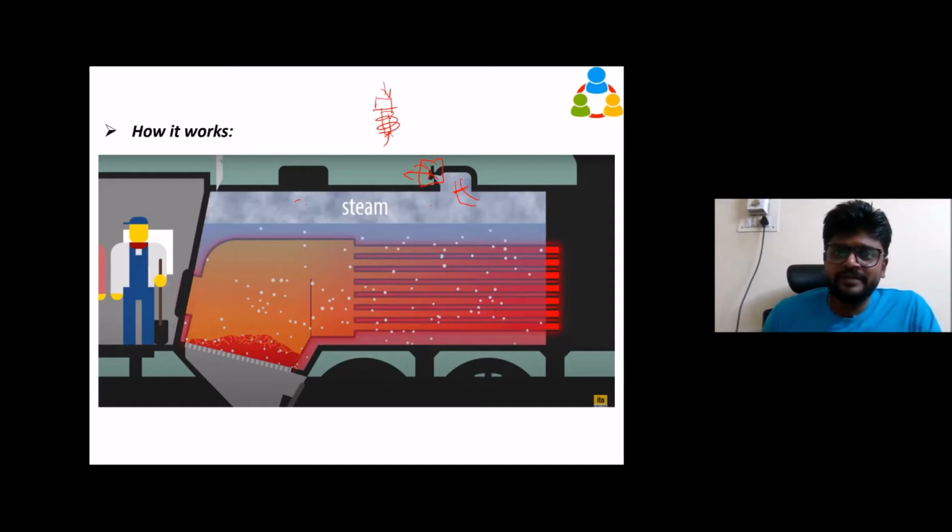So the pressure setting will be done with this spring tension. When the pressure is building up, this stud will come down and press against that spring. Here one opening will be there. Until then, this will be blocking that opening. Once the pressure reaches the spring force, the spring comes down, then the steam escapes through this valve.